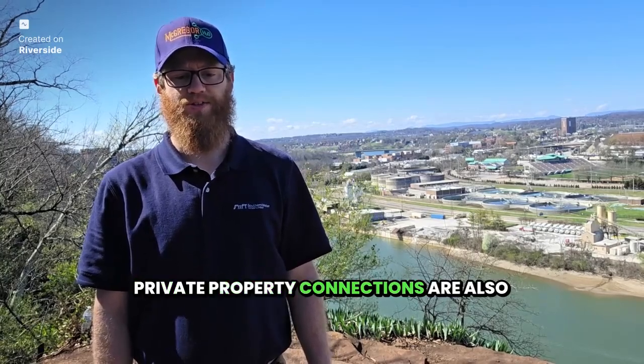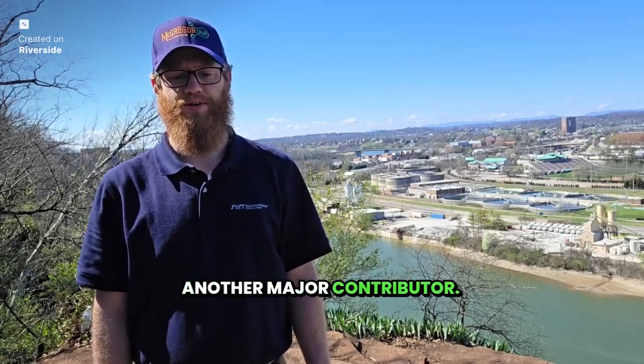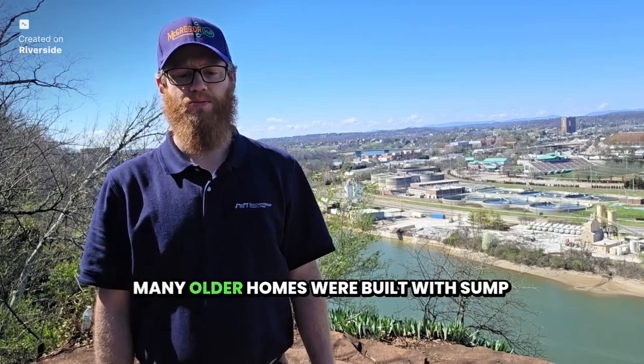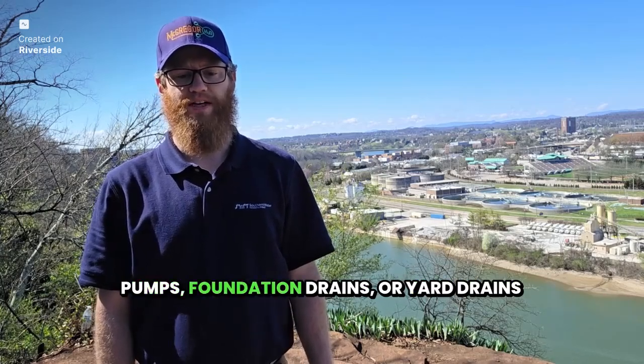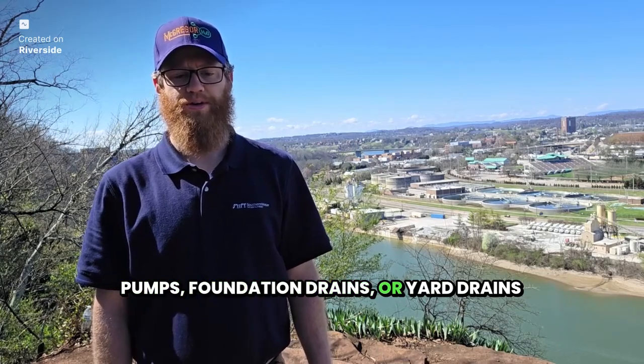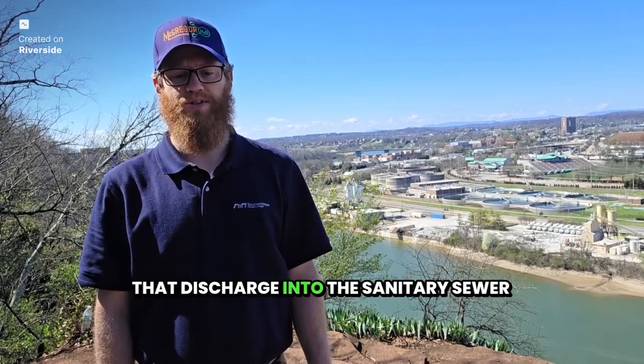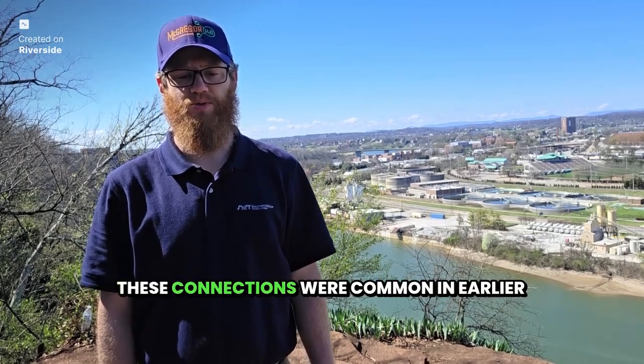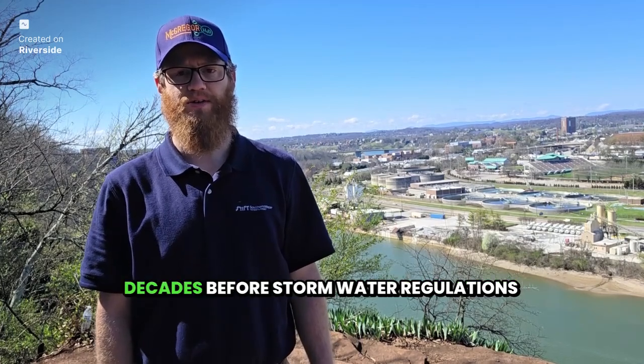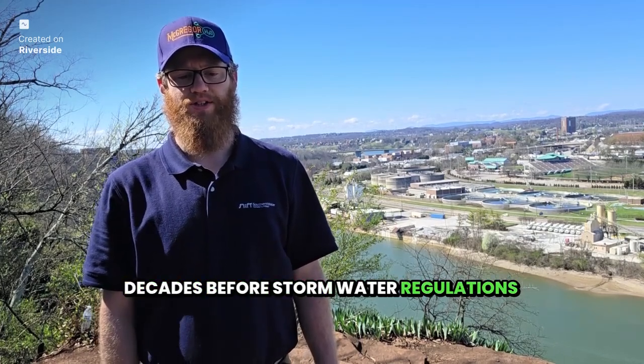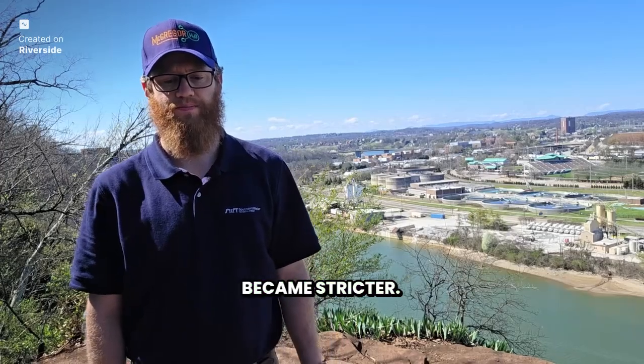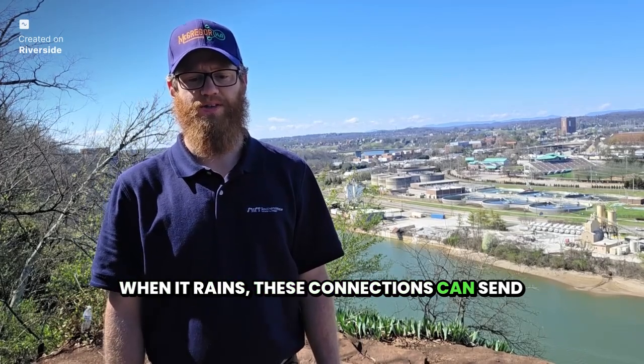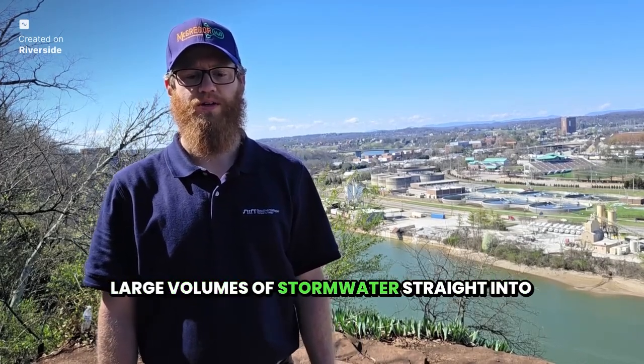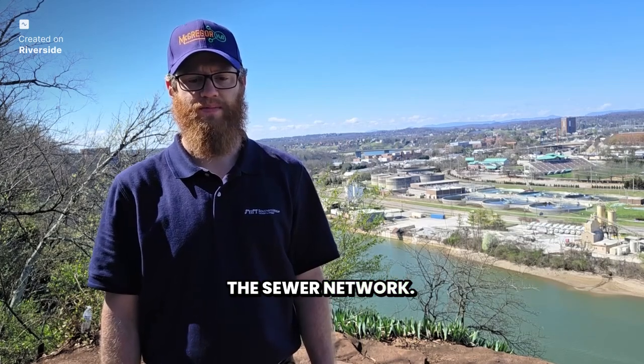Private property connections are also another major contributor. Many older homes were built with sump pumps, foundation drains, or yard drains that discharge into the sanitary sewer system. These connections were common in earlier decades before stormwater regulations became stricter. When it rains, these connections can send large volumes of stormwater straight into the sewer network.